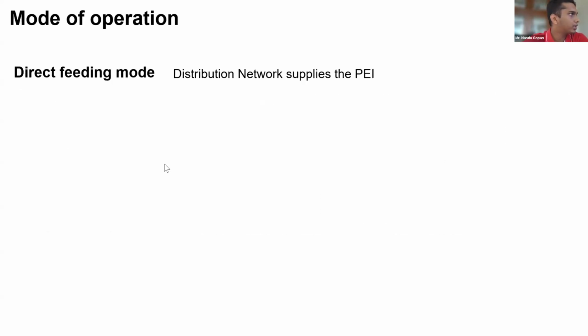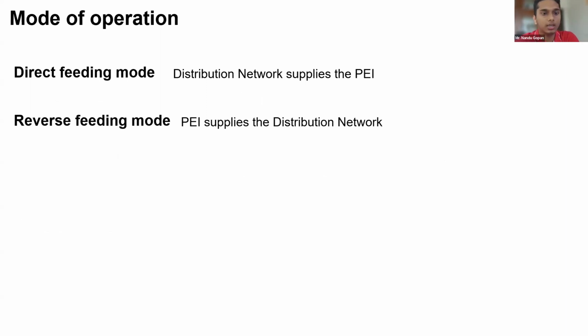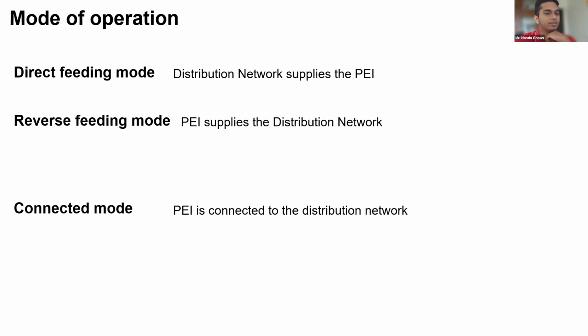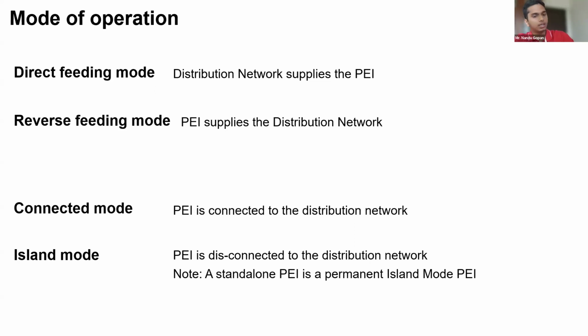Now to the modes of operation. There are two modes depending on how the feeding occurs: direct feeding and reverse feeding mode. These two are pretty obvious. Direct feeding means the distribution network supplies the PEI, and in reverse feeding, the PEI supplies the distribution network. And there is also another mode of operation. When the PEI is connected to the discom, and the discom is disconnected and the PEI is operating on its own in the installation, then it is an island mode operation.